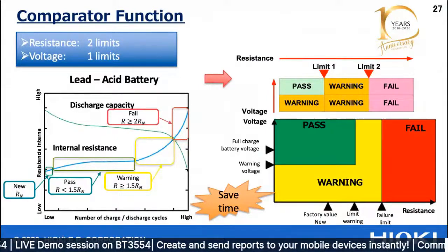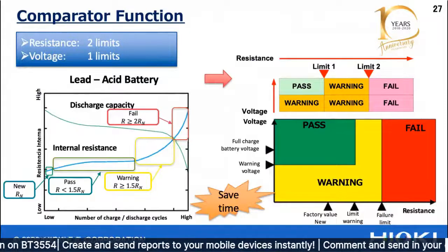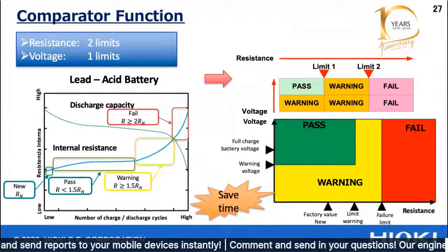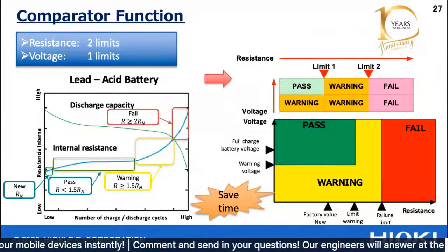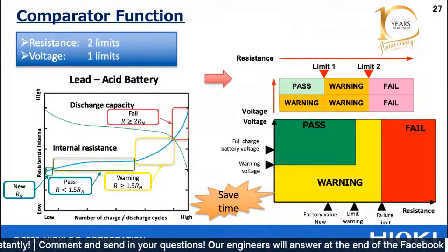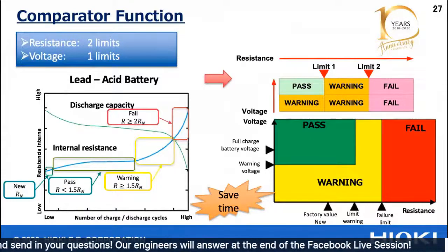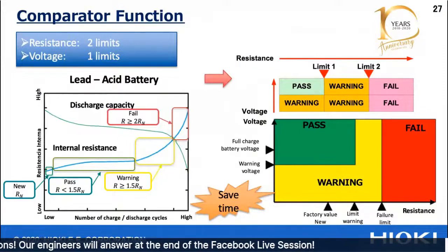For resistance, we need the reference value taken from a new battery. Every time a new battery is installed, take the first measurement and keep a record of it. This value is usually very low, typically in the milliohm range.